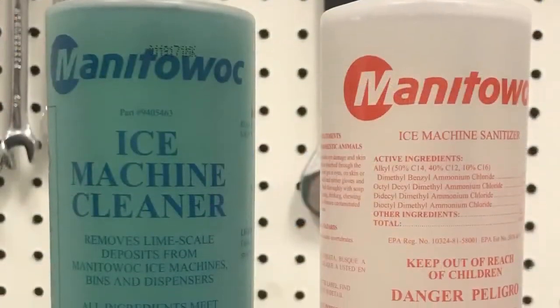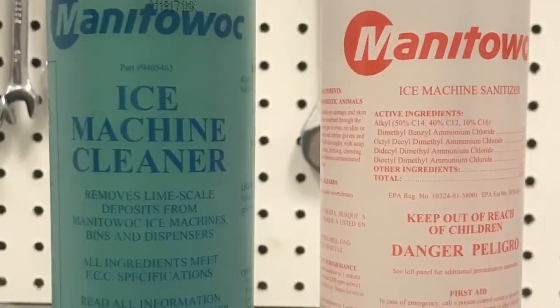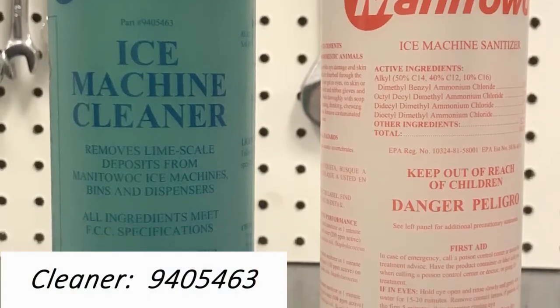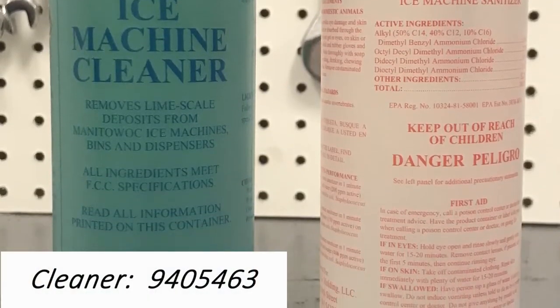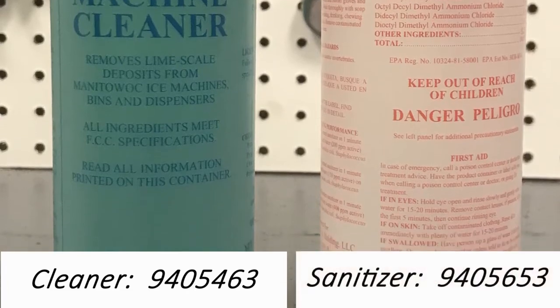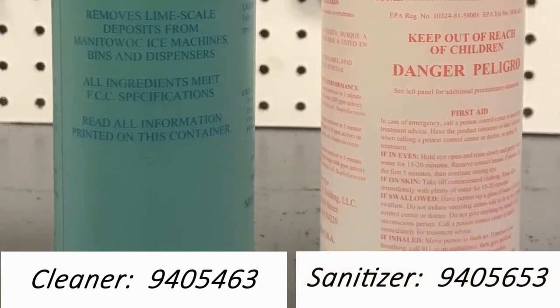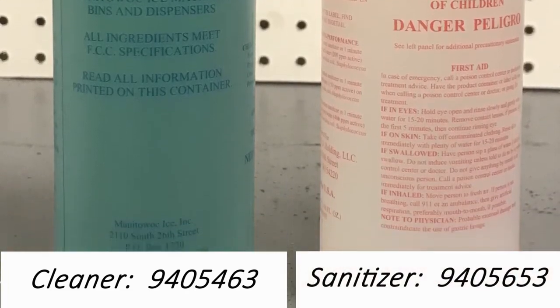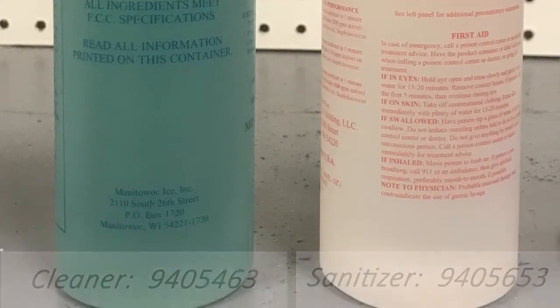Now it's very important you only use Manitowoc approved cleaners for cleaning ice machines, part number 9405463, and Manitowoc Ice Sanitizer, part number 9405653. While performing these procedures, do not mix the cleaner and sanitizer together, as the solutions would cancel each other out. Wear rubber gloves and safety glasses when handling the ice machine cleaner or sanitizer.